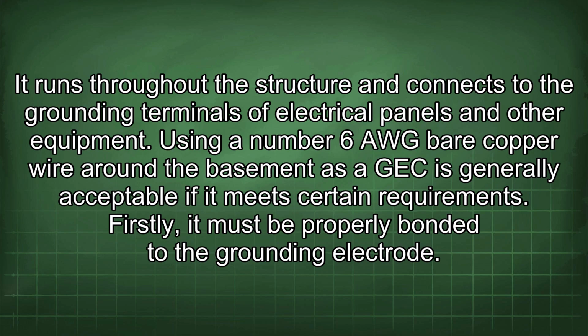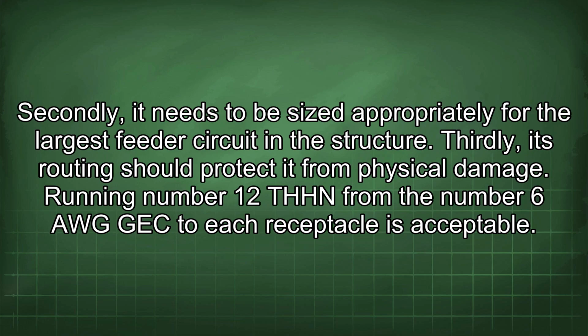Using a number 6 AWG bare copper wire around the basement as a GEC is generally acceptable if it meets certain requirements. Firstly, it must be properly bonded to the grounding electrode. Secondly, it needs to be sized appropriately for the largest feeder circuit in the structure. Thirdly, its routing should protect it from physical damage. Running number 12 THHN from the number 6 AWG GEC to each receptacle is acceptable.